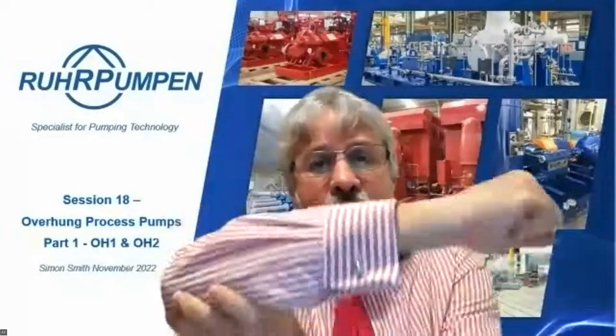Anonymous attendee, why are overhung pumps not recommended for flows exceeding 1,000 cubic meters an hour? You will have difficulty meeting the vibration requirements. Fundamentally the pump won't be reliable at the bigger sizes because it's an overhung pump and the loads are going up as you get higher and higher in flow. So at about those sort of flows, that's when a BB2 pump becomes a better option.